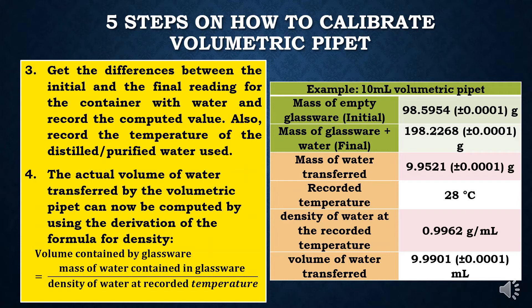Step 4: the actual volume of water transferred by the pipette can now be computed using the derivation of the formula for density. Volume is equal to the computed mass or weight of water transferred by the glassware divided by the density of water at the specified temperature. Since the recorded temperature of water is 28 degrees Celsius, with a corresponding density of 0.9962 grams per ml, 9.9521 grams divided by 0.9962 grams per ml gives 9.9901 ml, which is the volume of water transferred by the volumetric pipette.